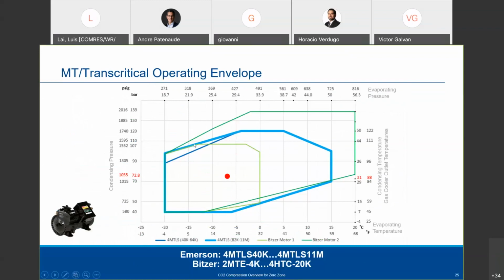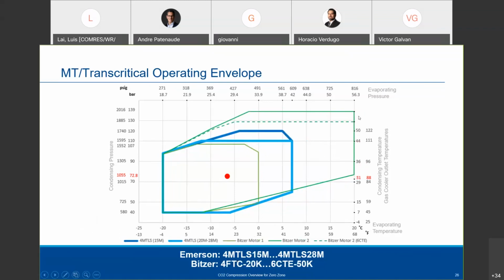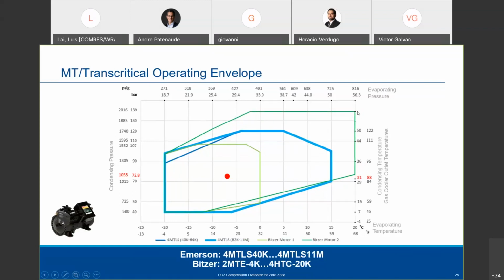Now, the light green in the middle here, that's Bitzer's motor 1 operating envelope. And the dark green is Bitzer's motor 2 operating envelope. Now, let's put it into context. Motor 2 operating envelope is not used in refrigeration. It's used for heat pump, or in areas where it is so bloody hot that it's running extremely high all the time. Not very efficient, but it is what it is. But the refrigeration motor is number 1.